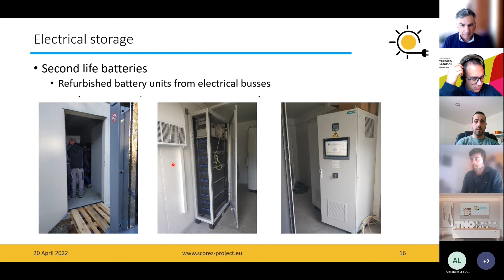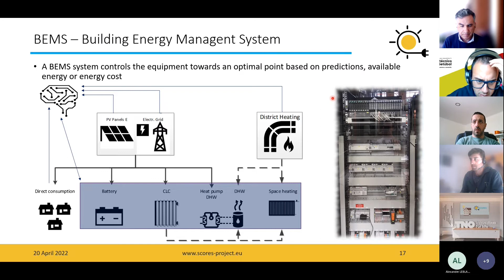So then everything is connected by a building energy management system, which controls the equipment toward an optimal point based on predictions—of the weather, the demand side, the available energy, and energy cost. This connects everything together: the battery, the CLC, the heat pump, the space heating, the grid and the district heating, and it can decide what to use when and when to store what. This is a rack with all the servers and equipment where the BEMS runs.